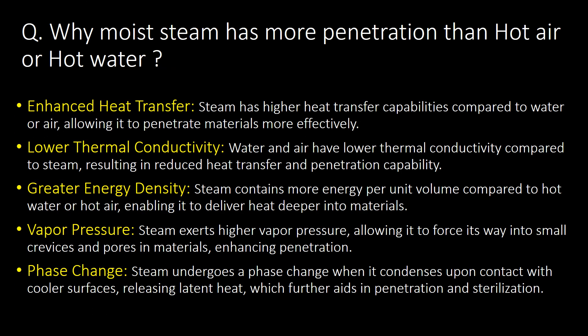Why does moist steam have more penetration than hot air or hot water? Here are five properties that make moist steam more penetrable. First is enhanced heat transfer — steam has higher heat transfer capabilities compared to water or air. Second is lower thermal conductivity — water and air have lower thermal conductivity compared to steam. Third is greater energy density. Fourth is vapor pressure — steam exerts higher vapor pressure, allowing it to force its way into small crevices and pores in material.